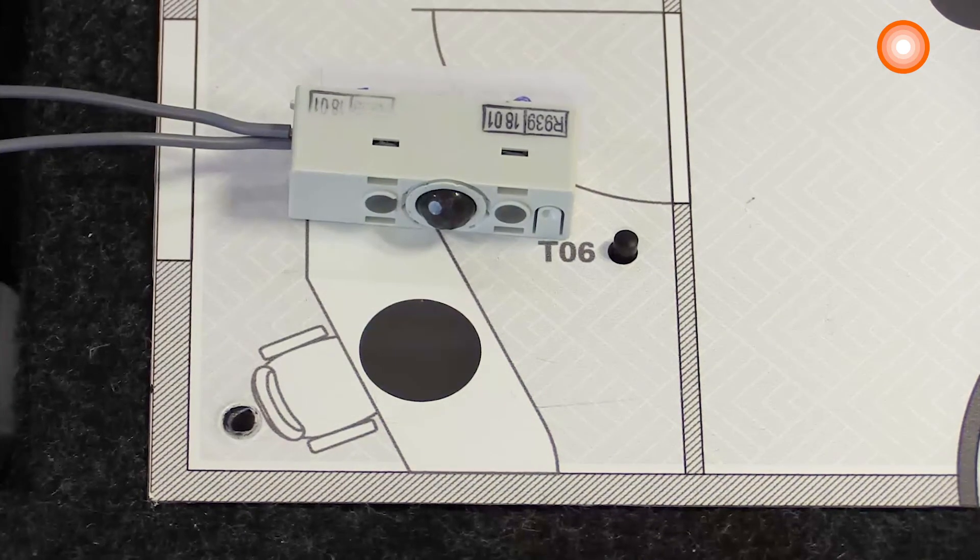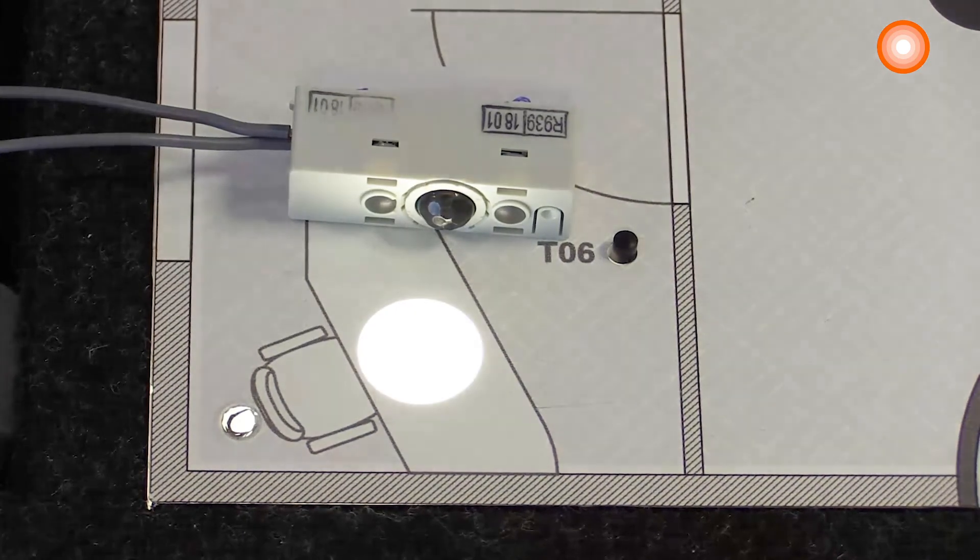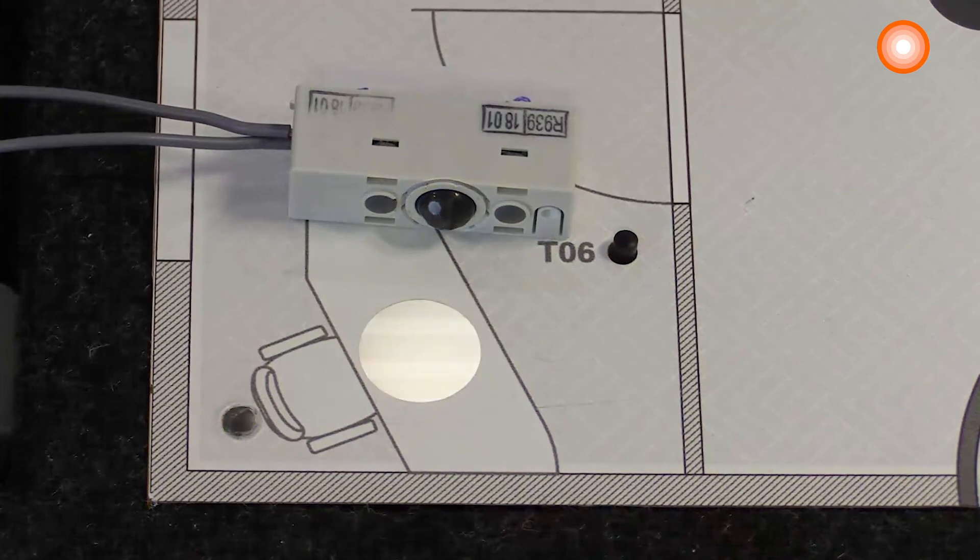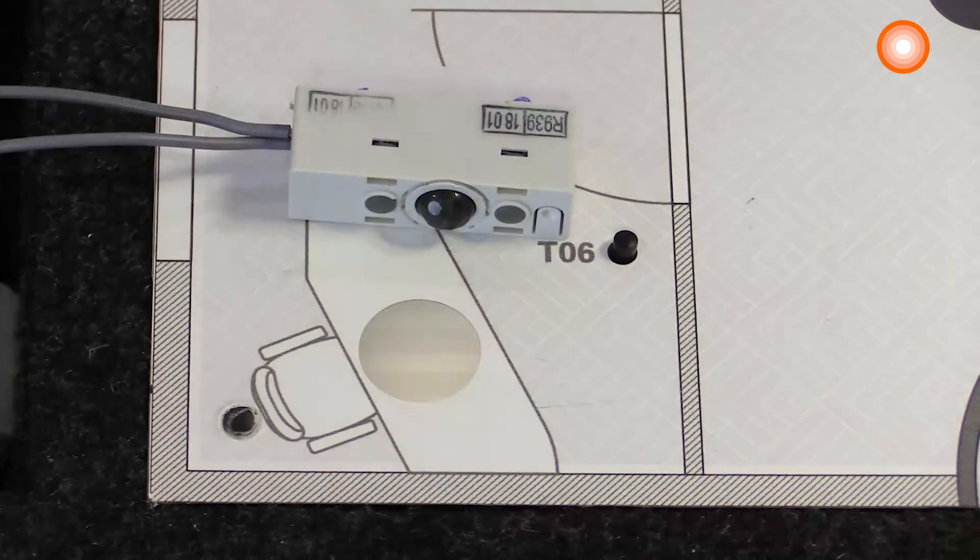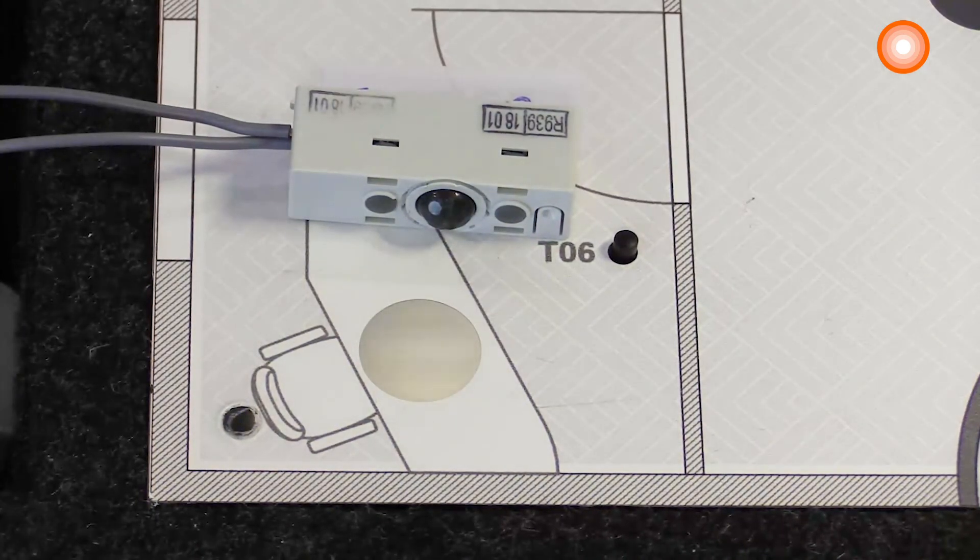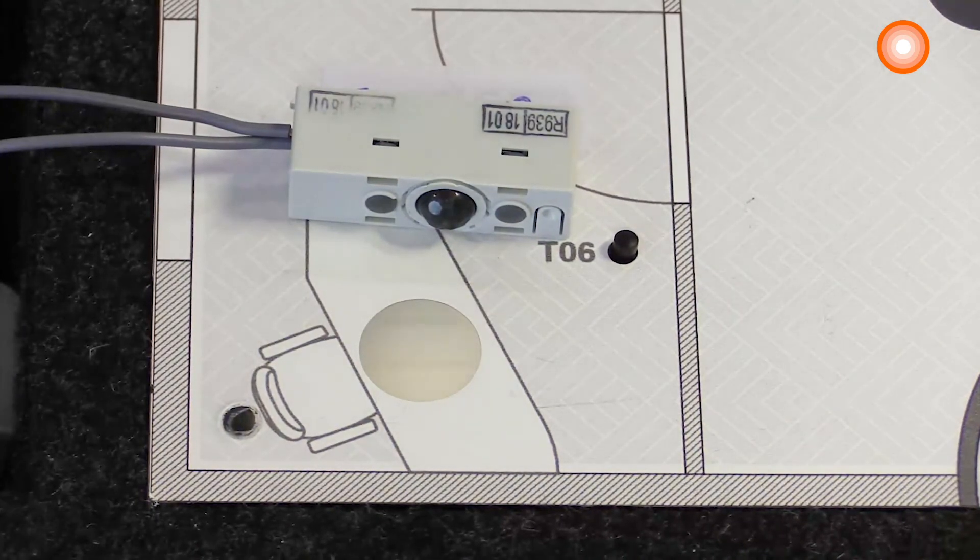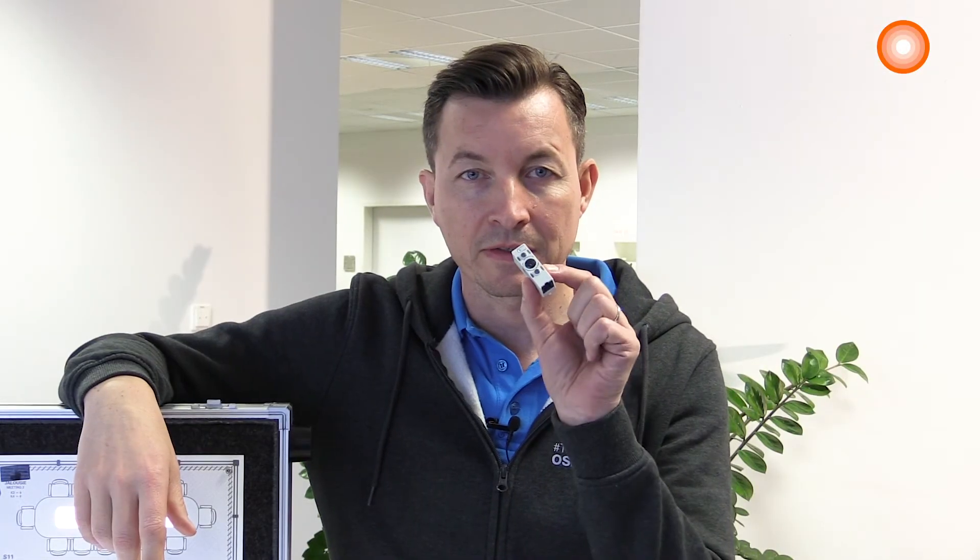The sensor can measure the daylight plus the artificial light, and the difference will be our calibration result. For a successful daylight calibration, make sure that you are not calibrating when it's completely dark or with full daylight.